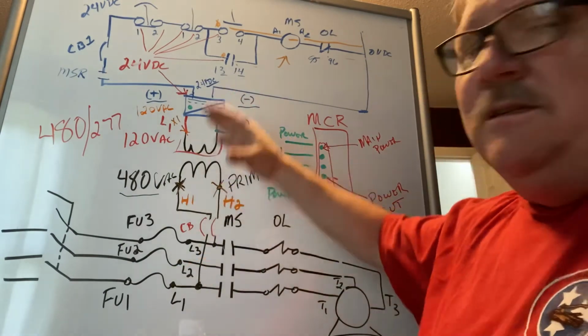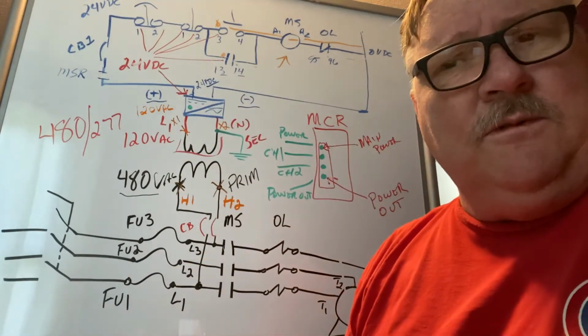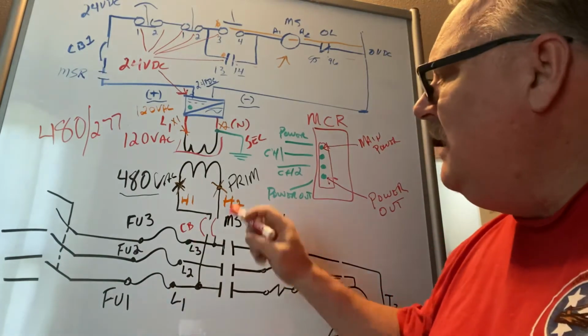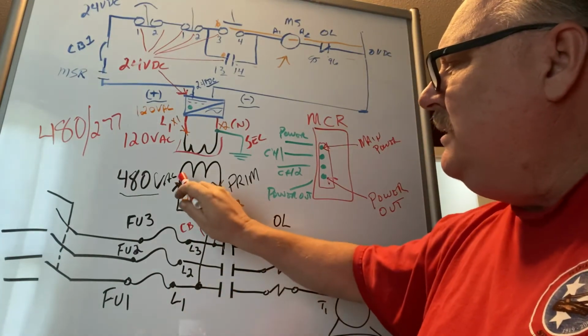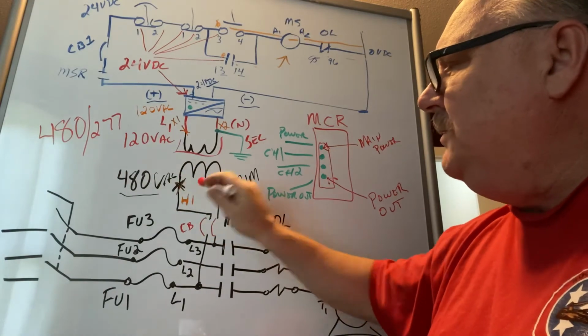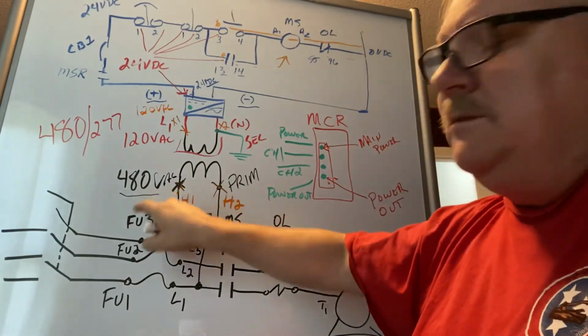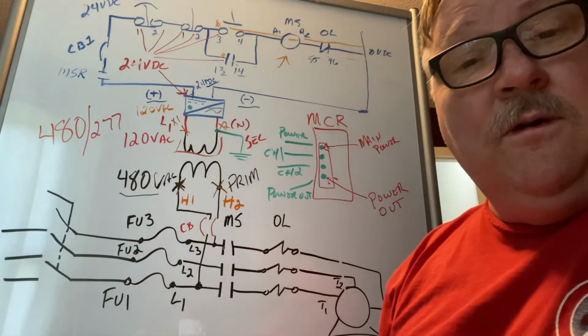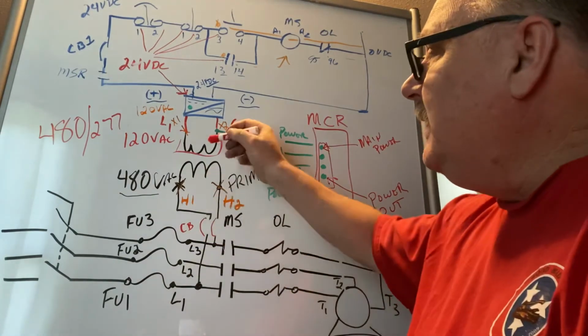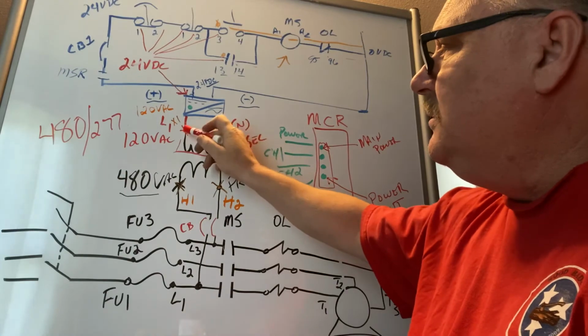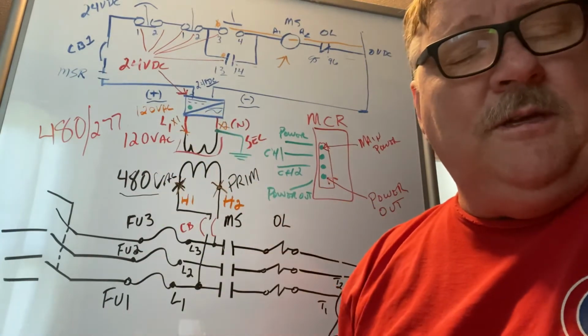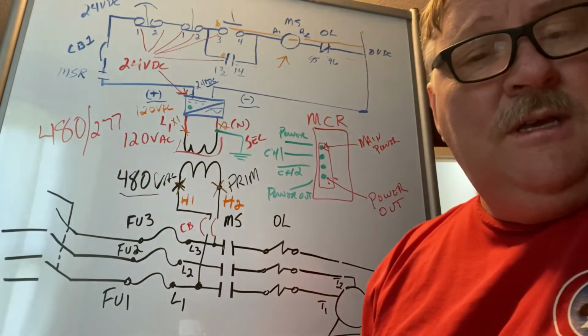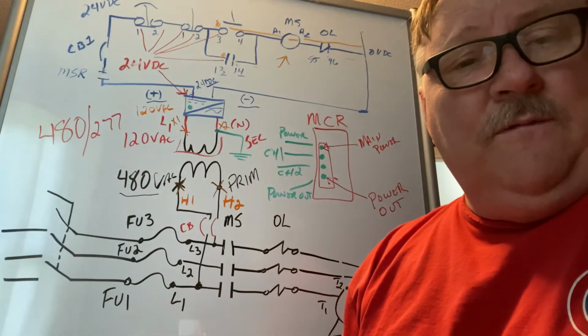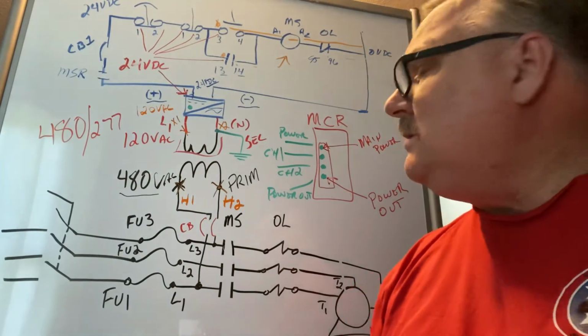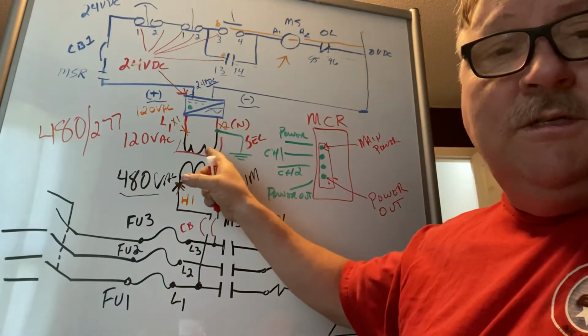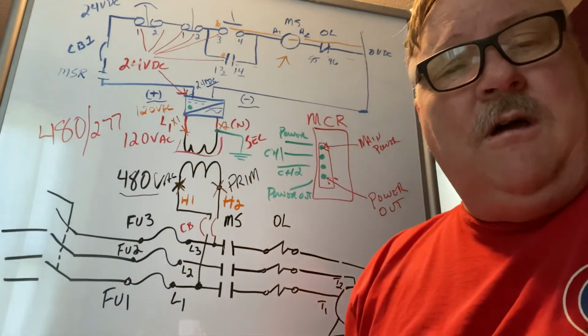All right, so we're going to get into some details on troubleshooting this, because transformers will give you some fits on certain things. But bottom line, if all your circuit breakers are right, you should be able to go from H1 to H2, and you should get whatever your system voltage is for the power circuit, 480 volts. On the secondary side, you should be able to go from X1 to X2, and you should get your 120 volts. If you don't get your 120 volts, but you have power here and there's no fuses involved, then you probably got a transformer that's gone bad on you.